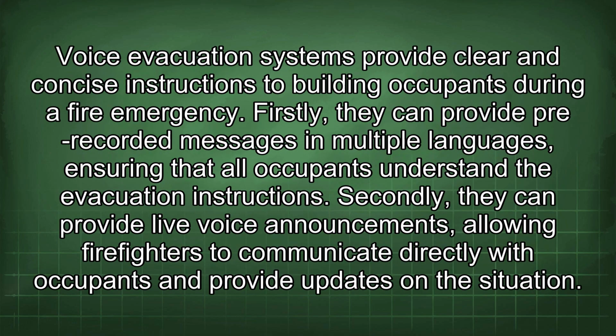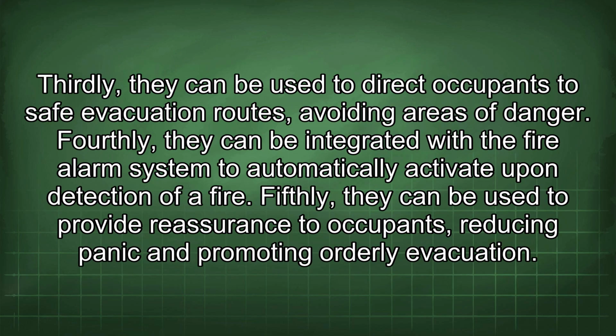Voice evacuation systems provide clear and concise instructions to building occupants during a fire emergency. Firstly, they can provide pre-recorded messages in multiple languages, ensuring that all occupants understand the evacuation instructions. Secondly, they can provide live voice announcements, allowing firefighters to communicate directly with occupants and provide updates on the situation. Thirdly, they can be used to direct occupants to safe evacuation routes, avoiding areas of danger. Fourthly, they can be integrated with the fire alarm system to automatically activate upon detection of a fire. Fifthly, they can be used to provide reassurance to occupants, reducing panic and promoting orderly evacuation.